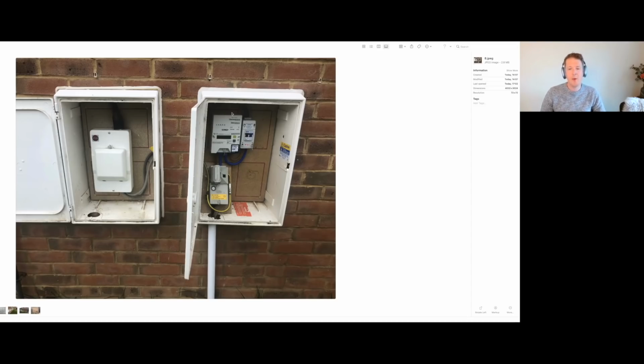So it looks like we might have the possibility here to run from one of these boxes. Now, actually, it looks like we've got enough space here to put a mini consumer unit, but I always try to avoid putting anything in there because we're not really supposed to. So my idea then is, could we potentially add something in here? Now, obviously, there's not enough room at the moment, but could we remove this switch fuse and install instead a two-way consumer unit, maybe with a surge protection device built in as well? And one circuit would then feed the main house consumer unit, and the other circuit would feed the electric vehicle charging point.